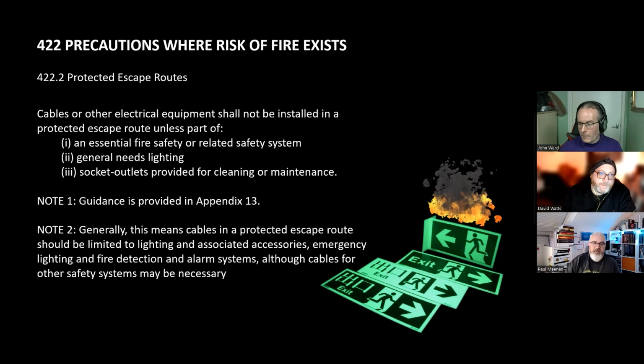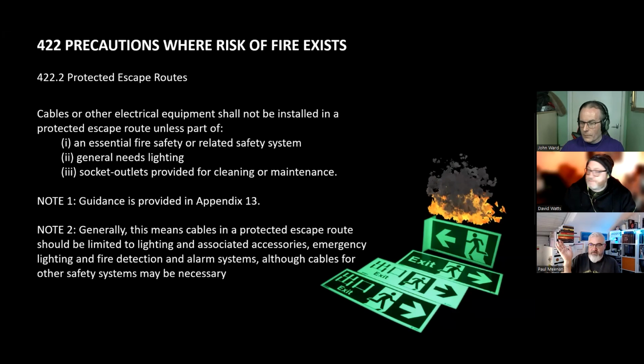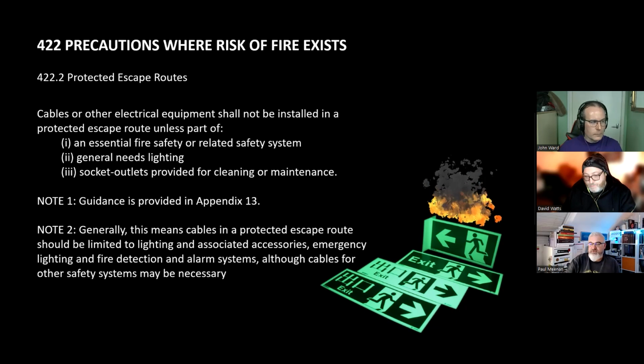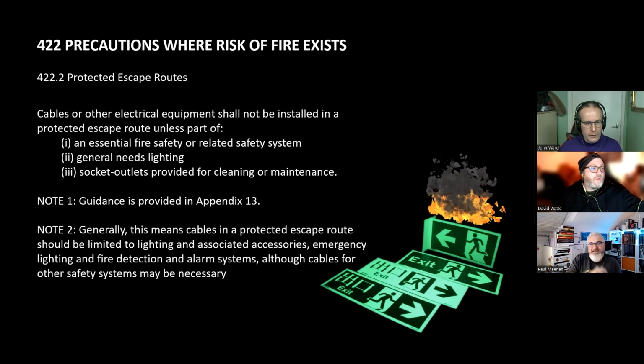Same principle. It basically states cables or other electrical equipment shall not be installed in a protected escape route unless part of the essential fire safety system, general needs lighting and emergency, or there's socket outlets provided for cleaning or maintenance. So if it's not relevant for that area, don't have it in there. A lot of social housing has submains running through these areas, all sorts. It's going to cause chaos. But again, these are recommendations.